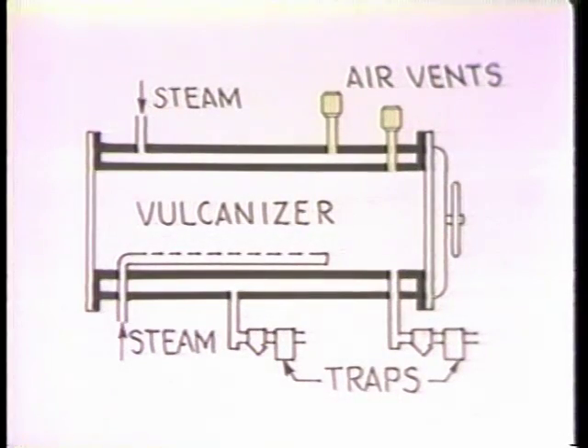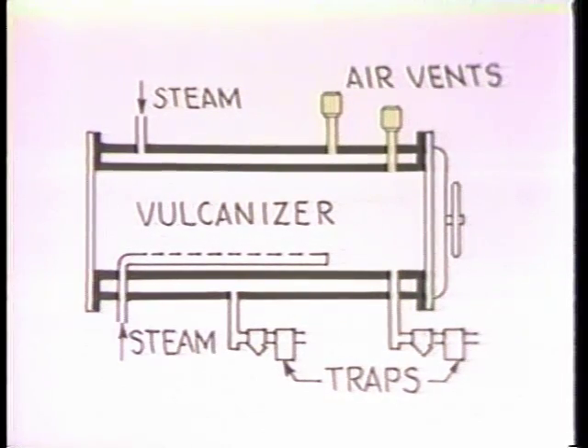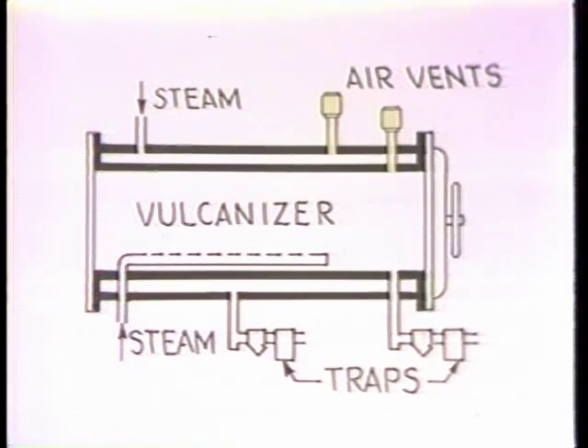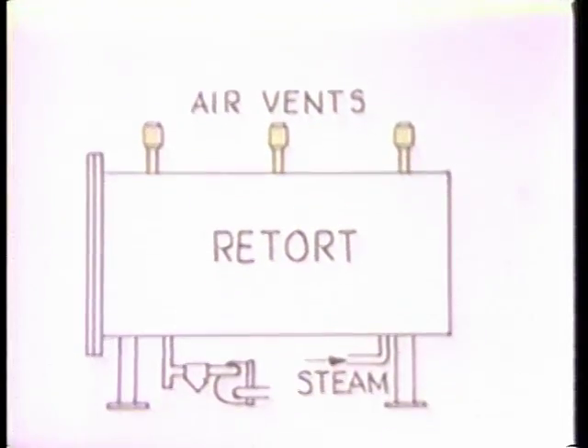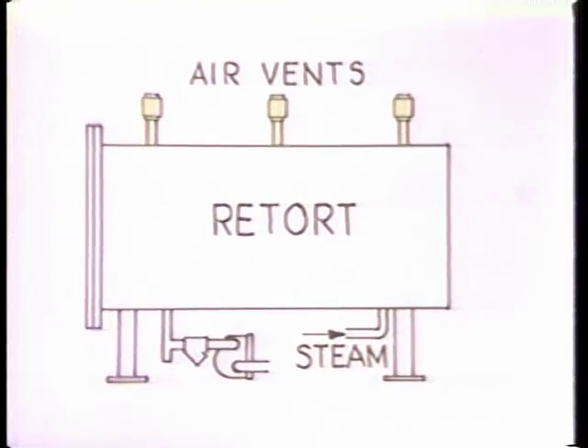One of the major factors in removing air from steam spaces is the location of the air vents. The air must be evacuated quickly to prevent mixing with the incoming steam and to achieve uniform temperature. Obviously, the place to install the air vent is where the air collects. Usually the air vent will be elevated above the highest part of the steam space to minimize liquid carryover through the vent.